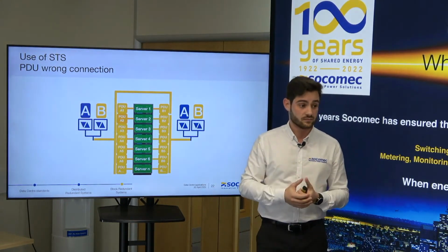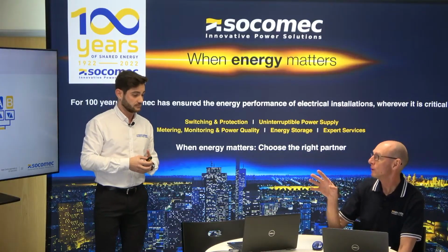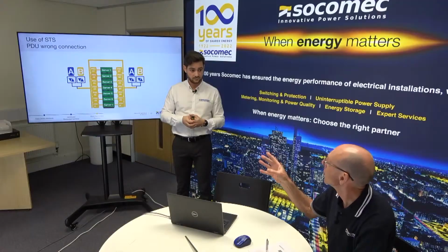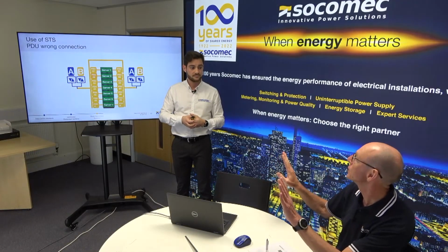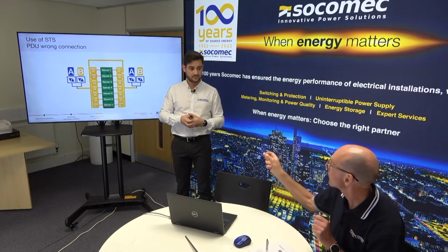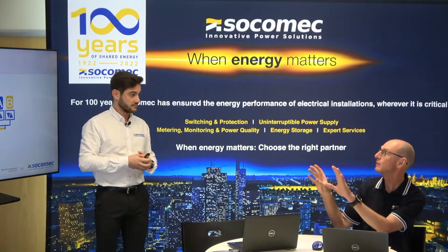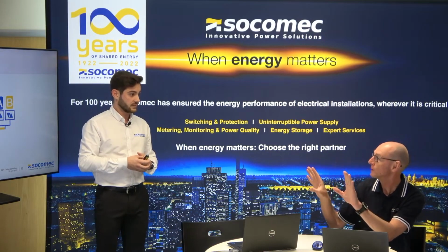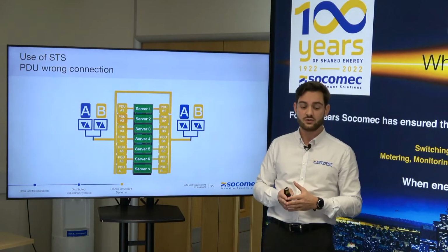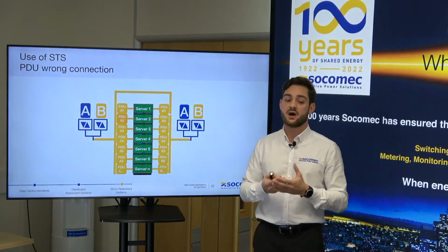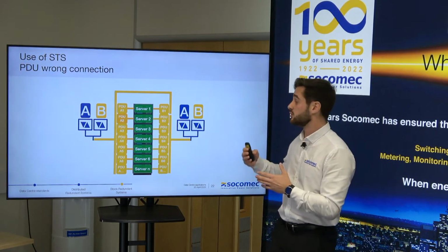So in the case we saw previously where one of the power supplies in the server had failed, by using STSs in the configuration, even though you might have a failed power supply on one of the paths, because you're now supplying it to both paths of B in this case, you're not going to lose that server. No, completely. So now we've understood the purpose of the STS and how it works. We can now move to the catcher UPS.